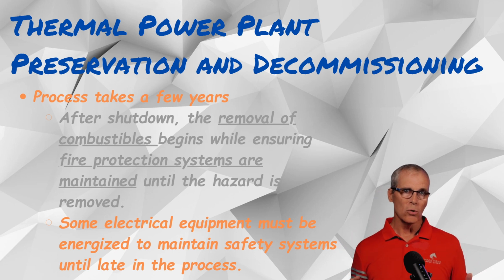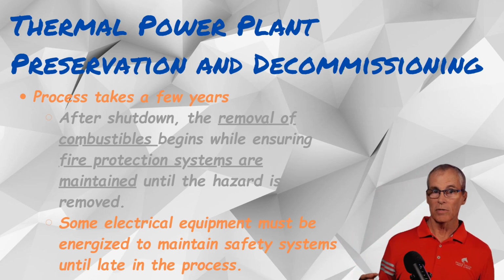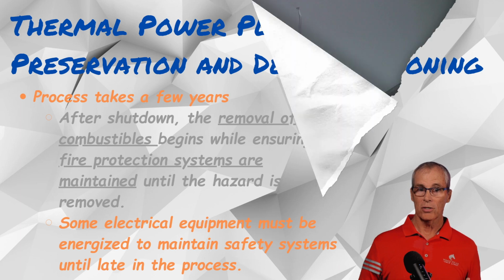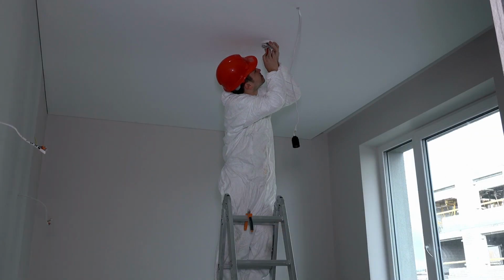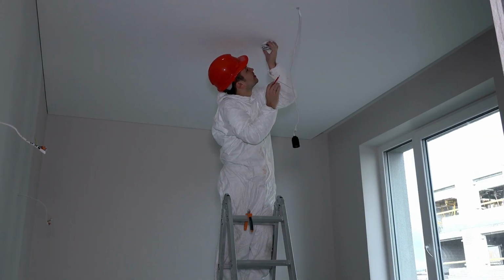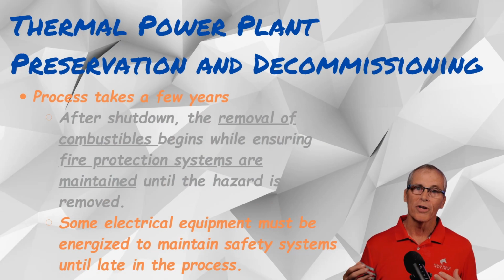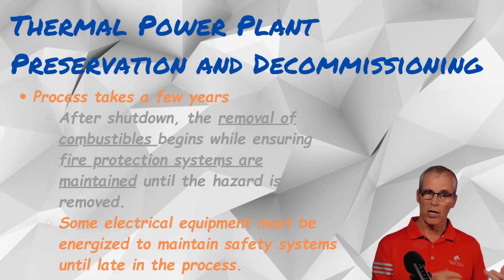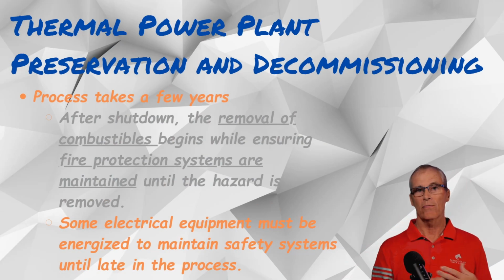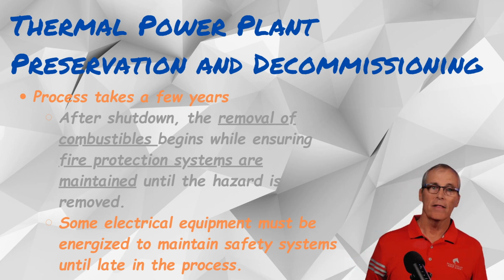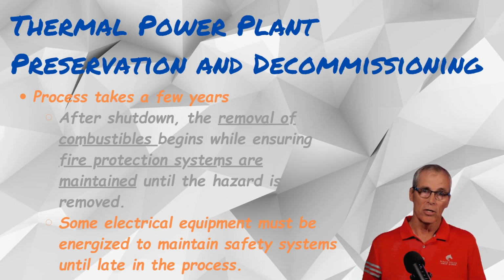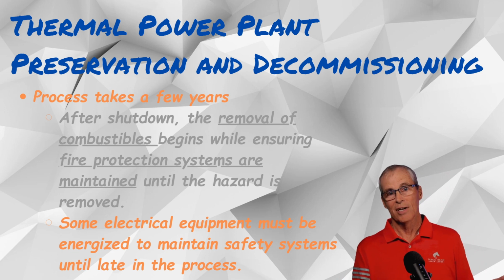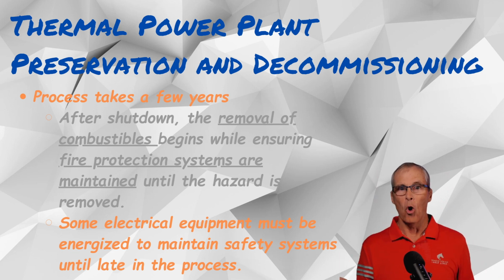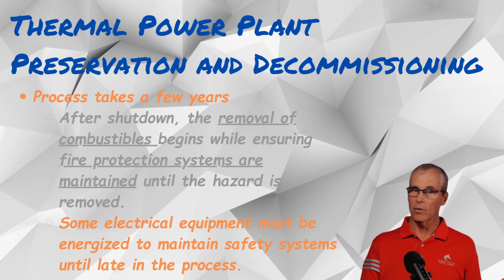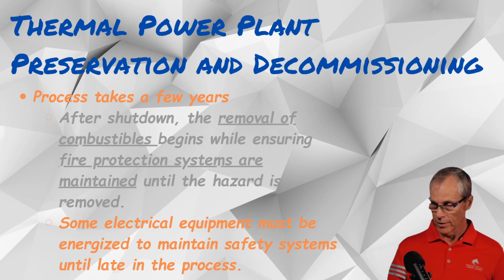The catch-22 a lot of times is that the fire protection systems need electricity — the detection systems do, and the actuation devices on some of the protection do. So what are you going to do when you need to remove the transformers providing power for the fire protection system? It's a chicken and egg situation. You keep the fire protection and services as long as you can, and when there's no other need for the electrical, you can pull it out.